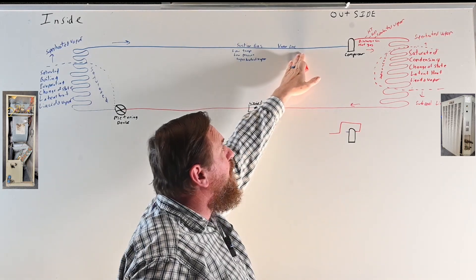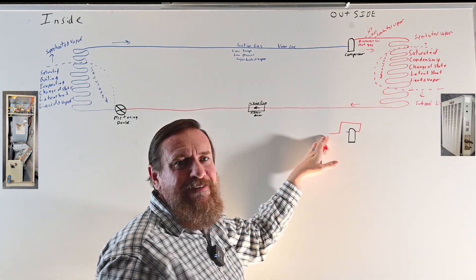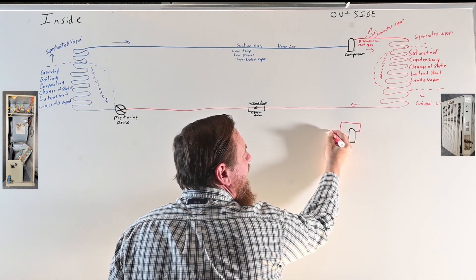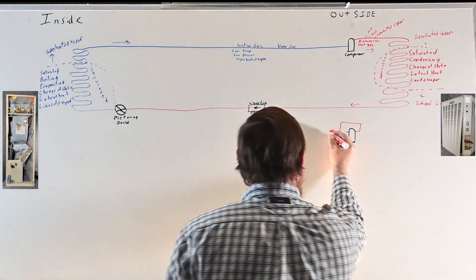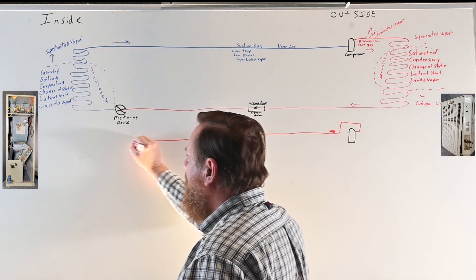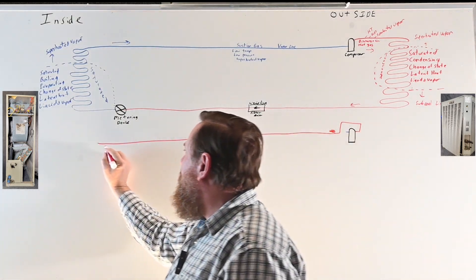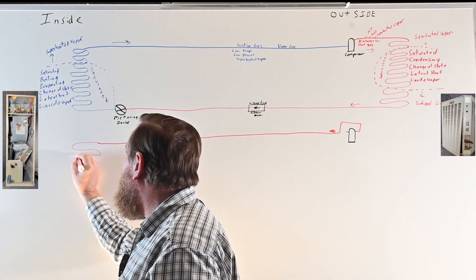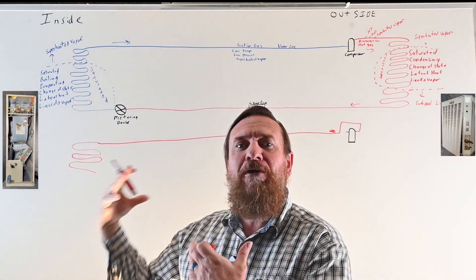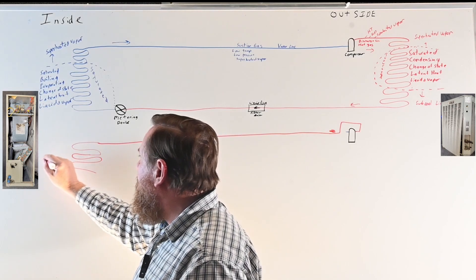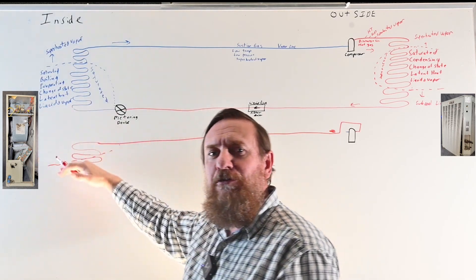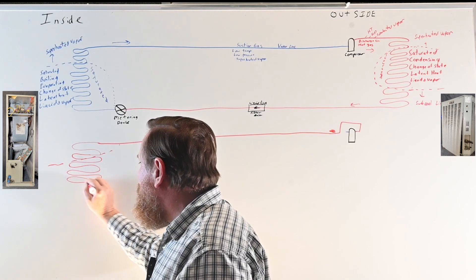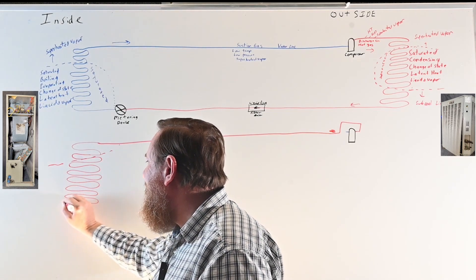It's still vapor, but now it's high temperature, high pressure, superheated vapor instead of low temperature, low pressure. We take this refrigerant and send it inside in the opposite direction — through the big fat line to the inside unit. We send it through what was once the evaporator coil, now acting as the condenser. It's warmer than the temperature of the air in the house, so the first thing we do is de-superheat it, then make that refrigerant change state from a vapor to a liquid.